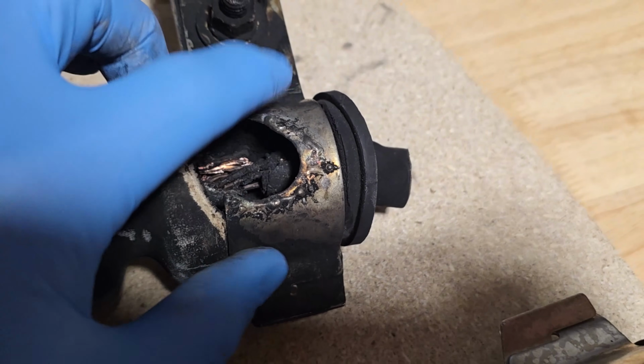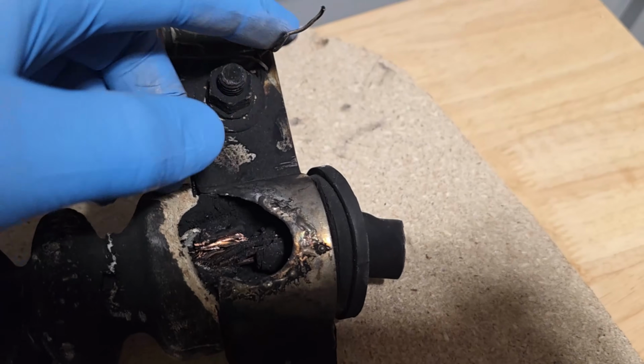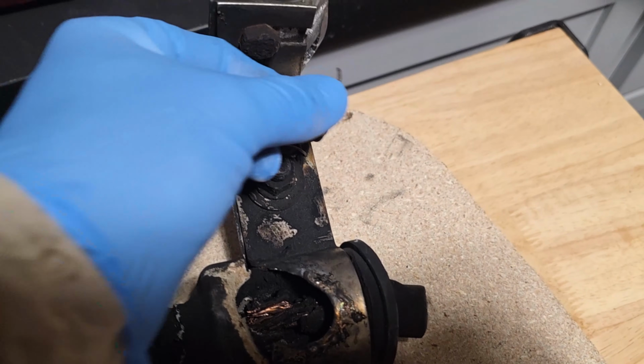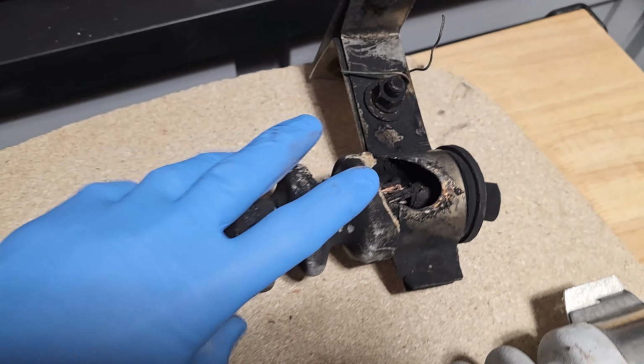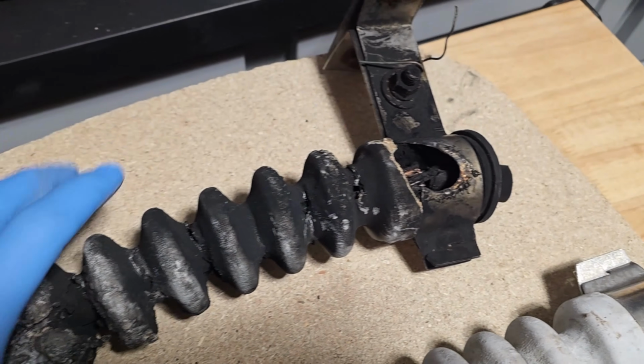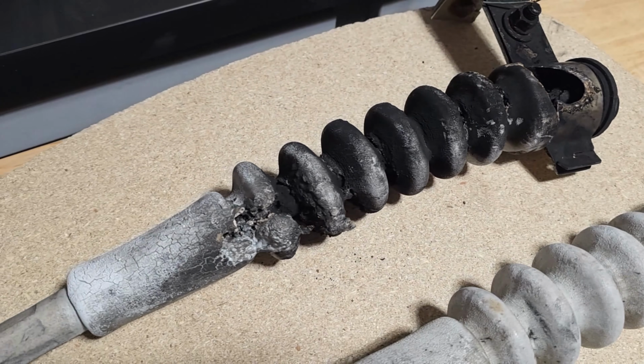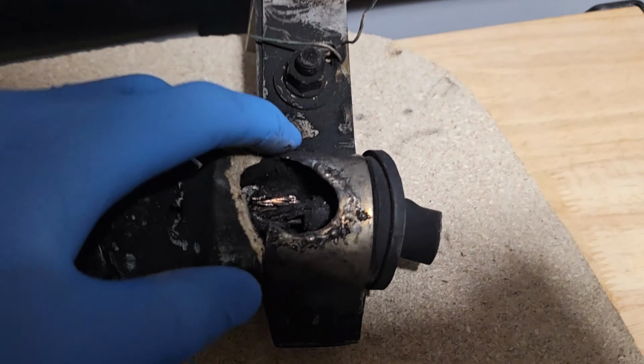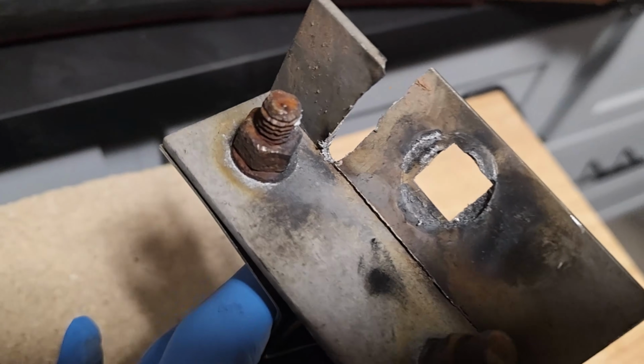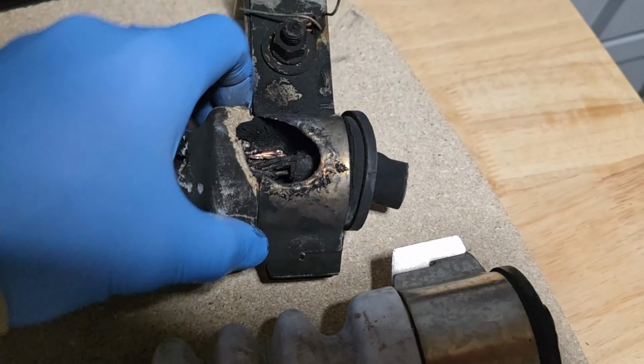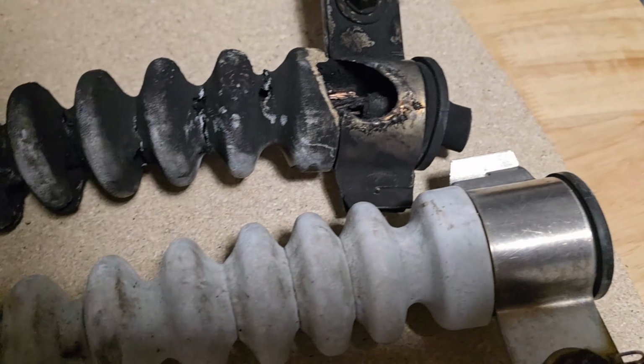There's a real solid reference to ground here that didn't really do much. That bleeder cable is just there so there's no stray static voltage building up on the insulator - you see them on all forms of terminations. But this bracket was tied directly to ground. There was a ground on the pole, so that's why it was such a catastrophic failure right there. That guy looks like it might pull right off.